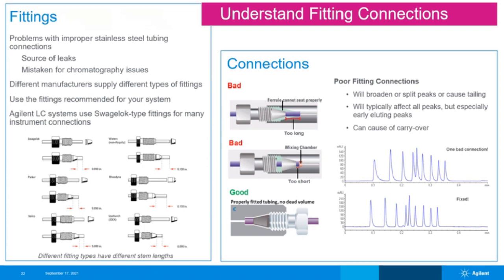The fittings. Proper seating of fittings is of utmost importance through all your LC connections. If the tubing extends too long past the fitting, the ferrule cannot seat properly and leaks will occur. If the tubing is too short past the ferrule, a dead volume is created and mixing can occur in this tiny void. This can broaden or split peaks or cause tailing, especially on early eluting peaks. It can also be a source of carryover. A properly installed fitting is perfectly flushed with zero dead volume.